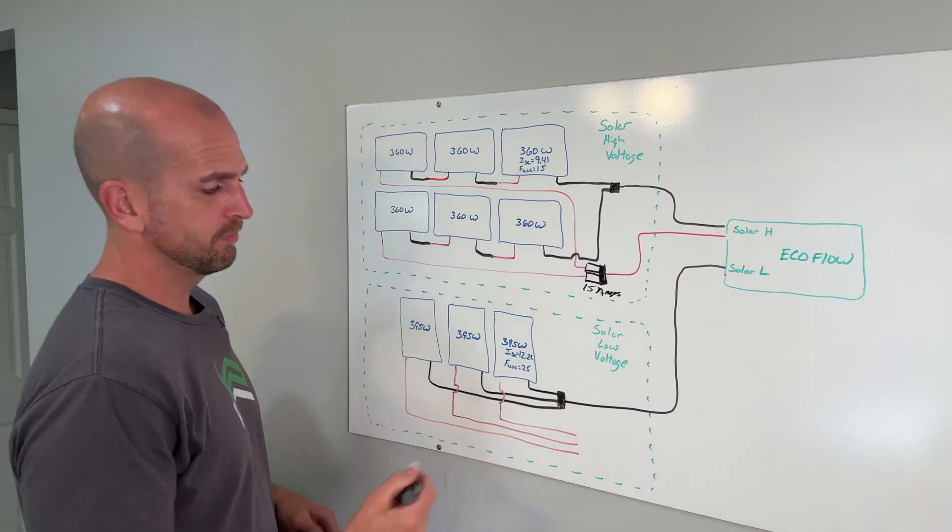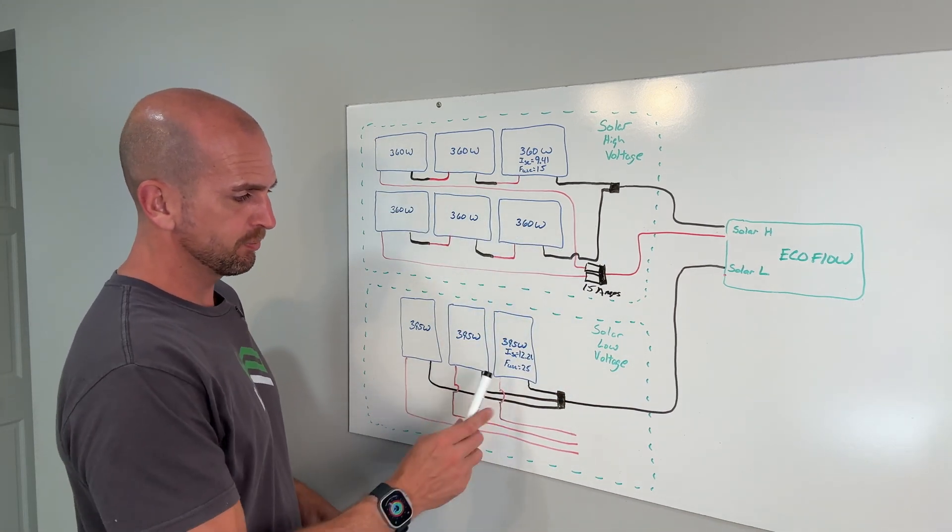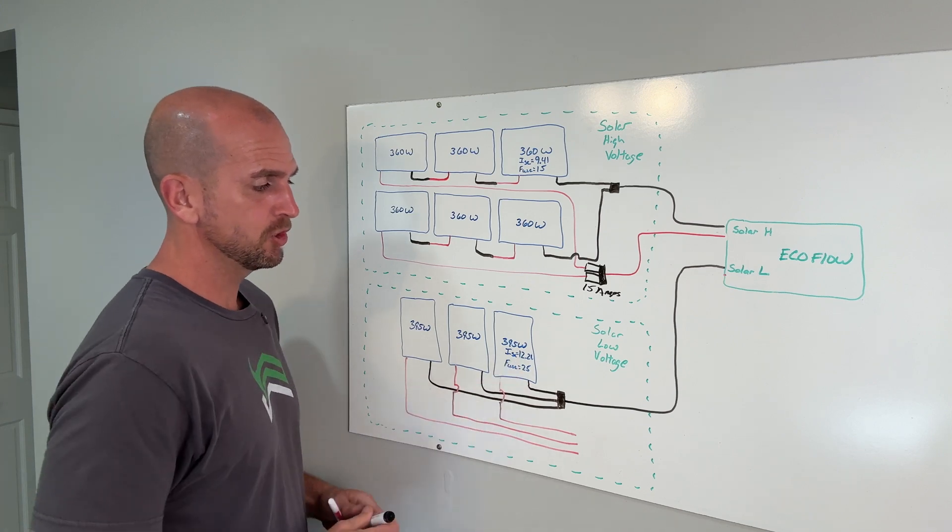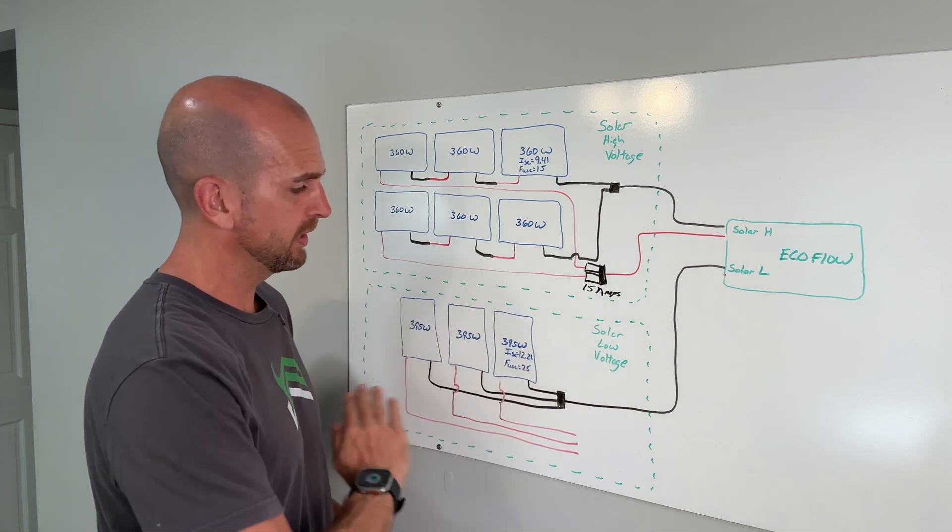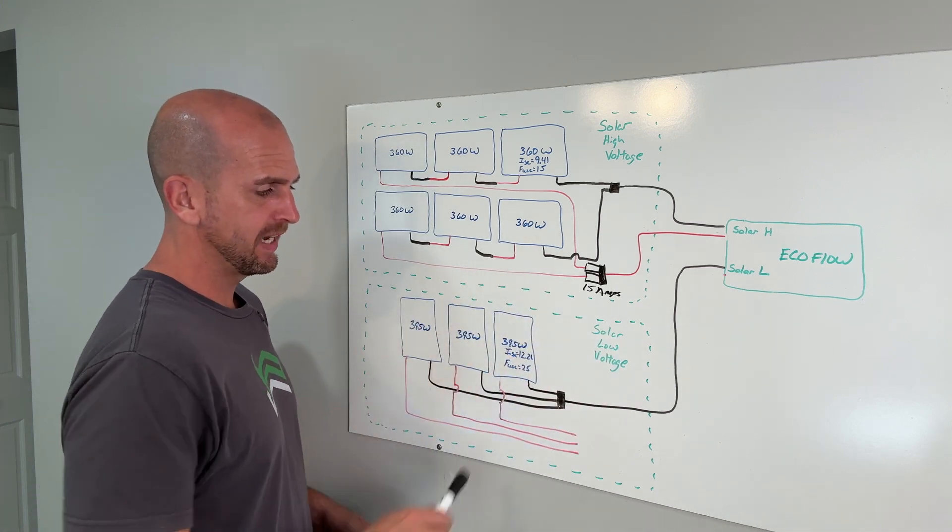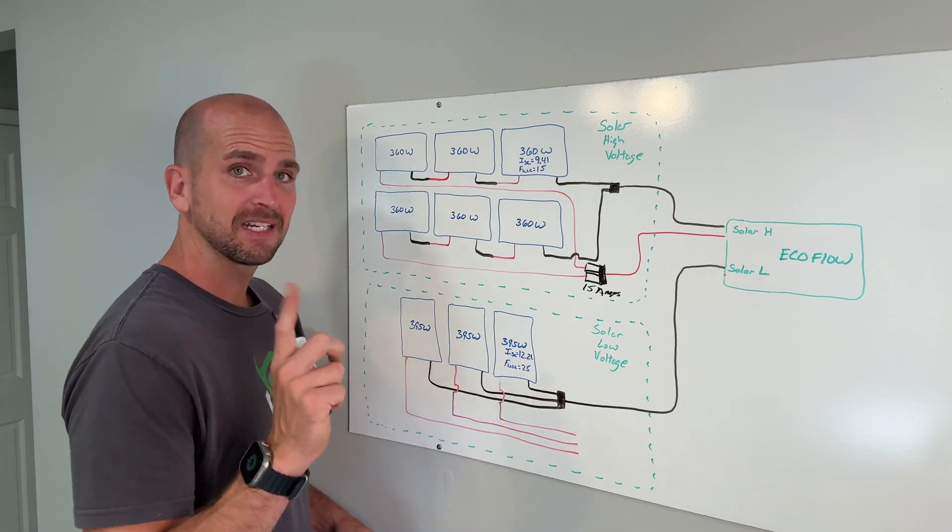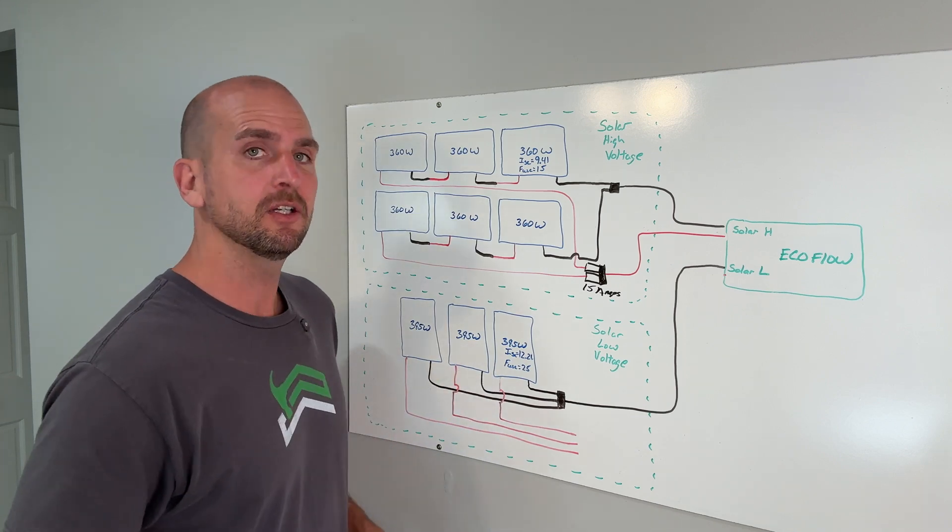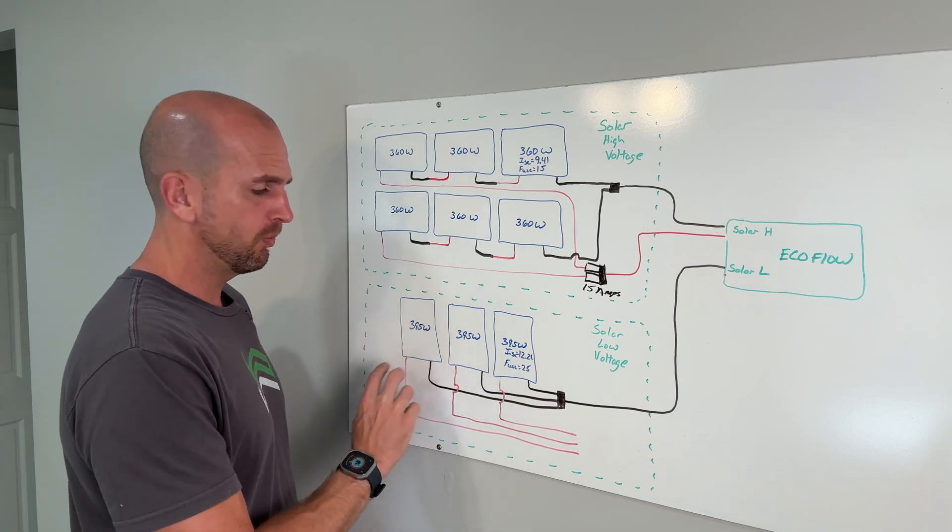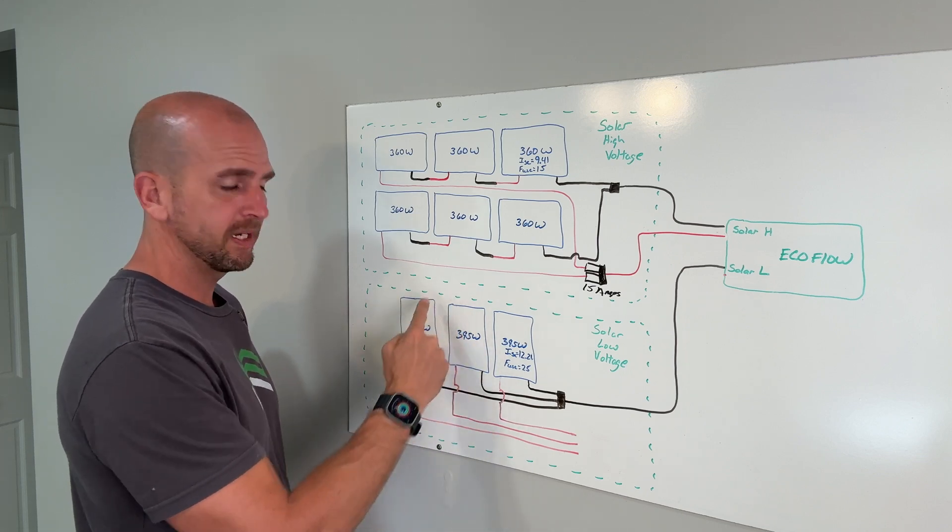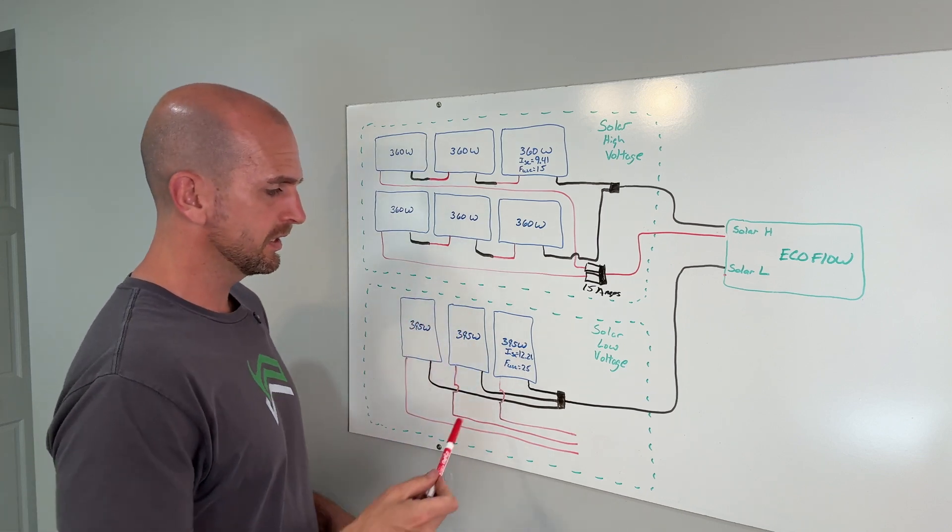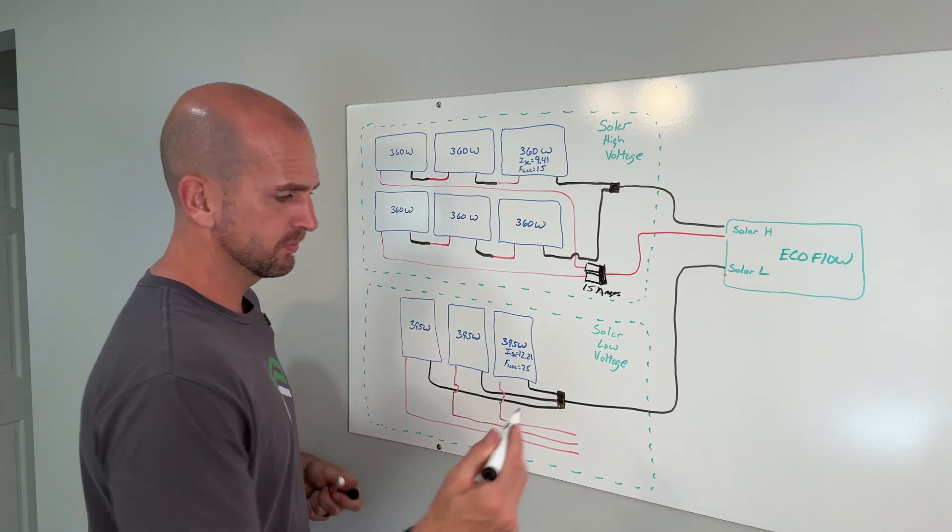Now looking at the bottom here we're going to bring three branches together so that's 12.21 times three, we are well over the 25. If we only had two of these coming together technically that would be under the 25 so we'd have parallel wiring configuration between two panels and we would not need any inline fuses. But here we do.